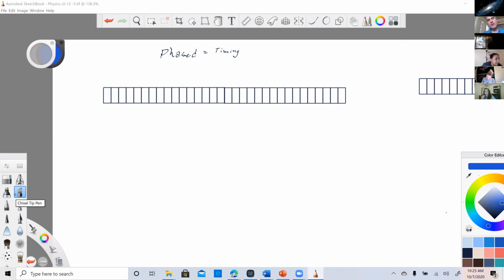When we talk about the first phased array we talked about all the way back on page 169, it was a linear phased array. It phases, but it doesn't sequence. So the linear phased array, in fact, almost every single beam it puts out is directed one direction or another. The phased array sends a beam off in this direction and then that direction and then that direction, and it ends up creating a triangular pie-shaped screen. There's no sequencing on the linear phased array, because every single element is used every single time. The timing is different, but every single one of them is used.